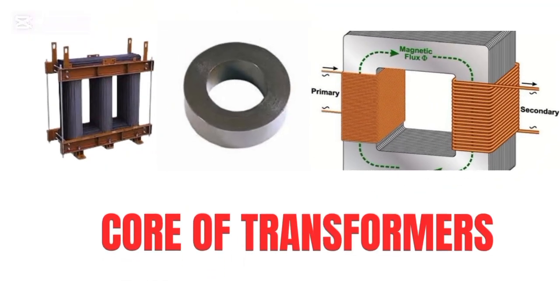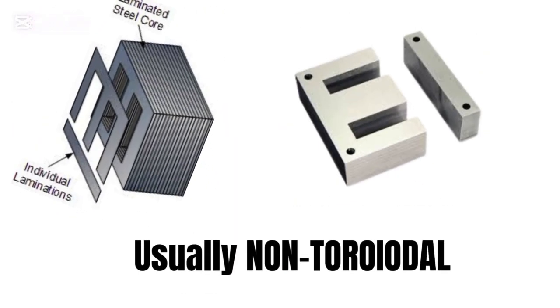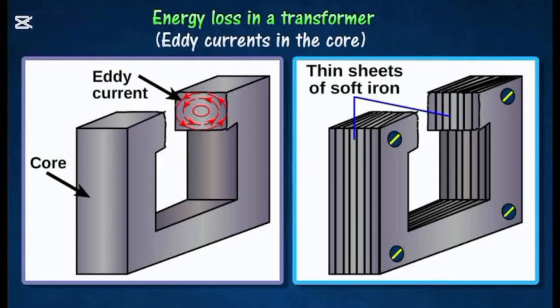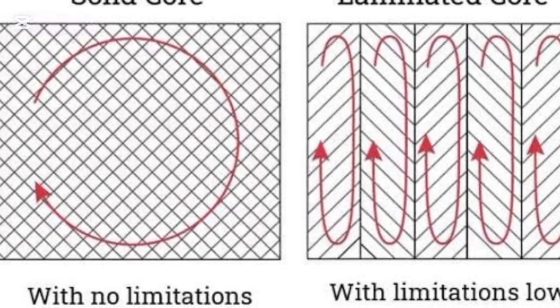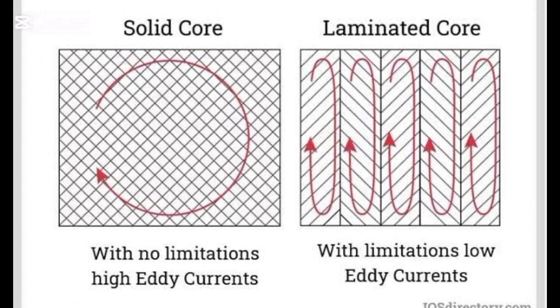The core of a transformer is made of special steel, cold rolled, grain oriented, or CRGO, and is built in thin layers or laminations to reduce energy loss. This design helps focus the magnetic field while reducing heating from unwanted currents. Laminations break up the flow of wasteful electric currents inside the metal.